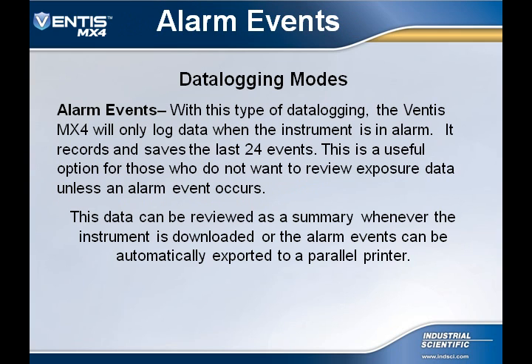With alarm event data log, the Ventus MX-4 will only data log when the instrument is in alarm. It records and saves the last 24 events. This information is useful if the user's only concern is when the instrument is in alarm. This data can also be exported to a printer to give the user a hard copy.